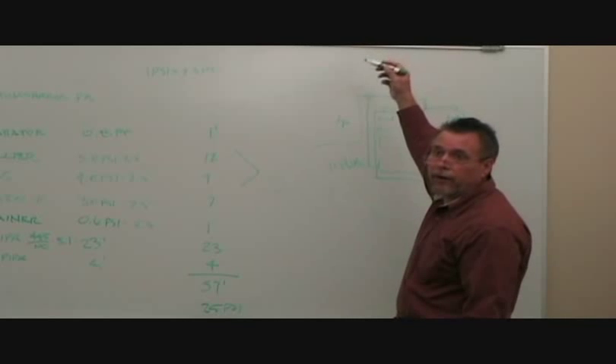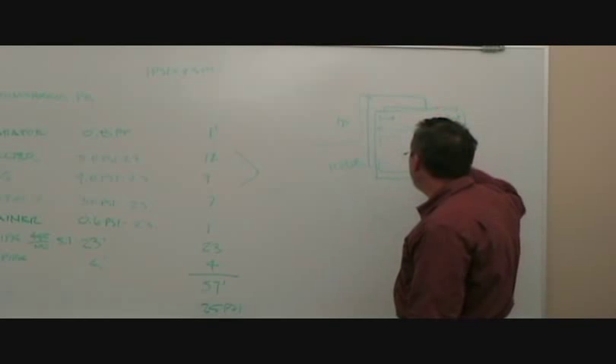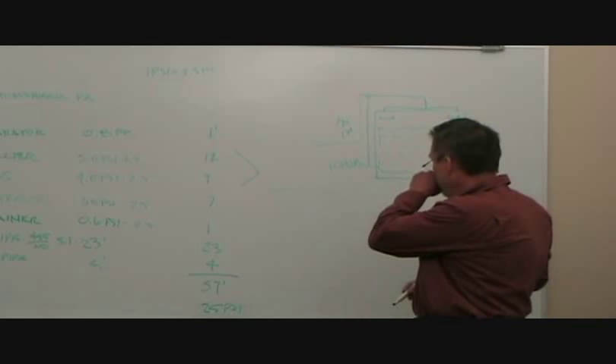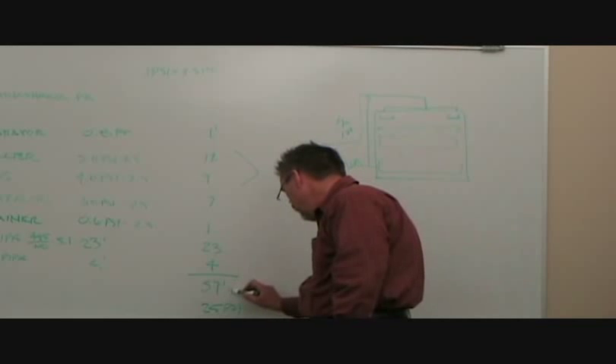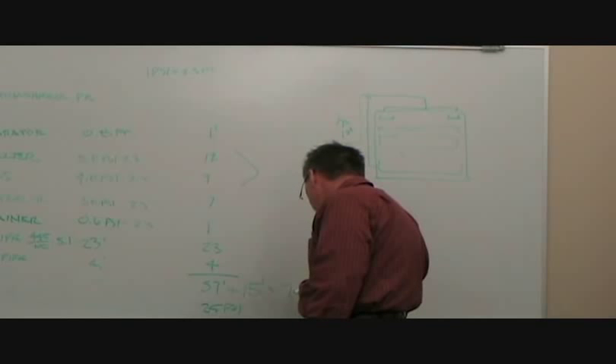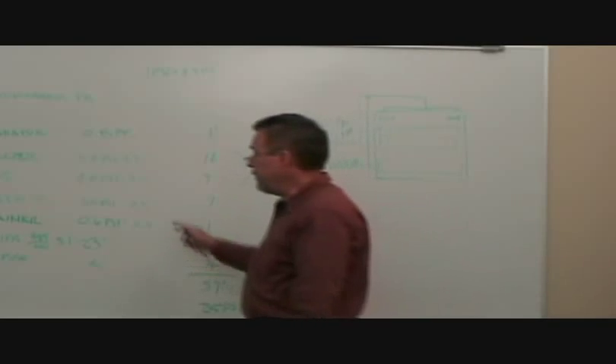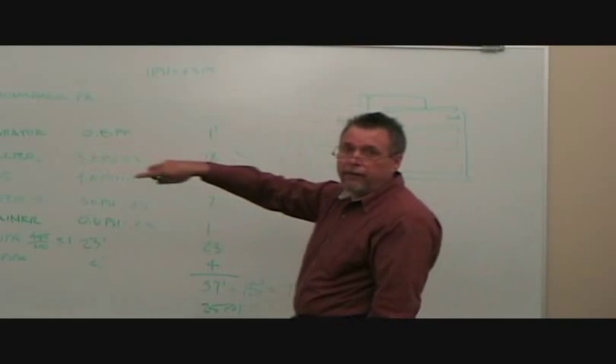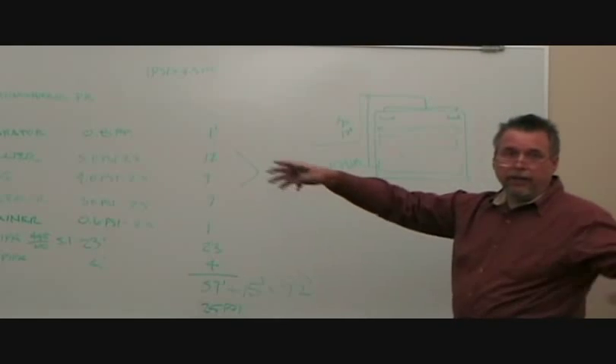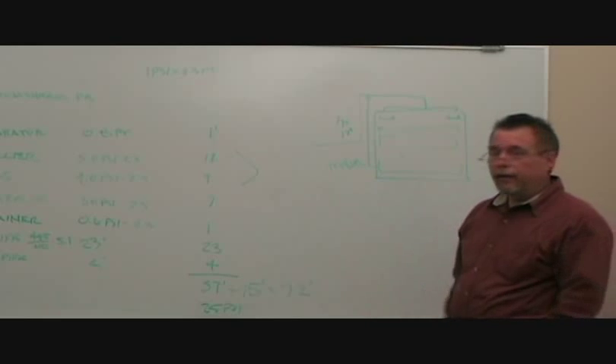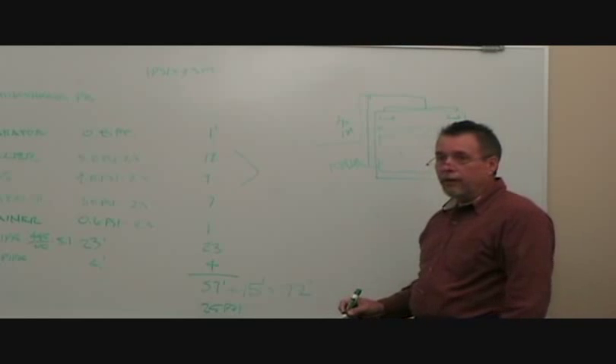Then I've got to lift that water up because it's open inside here, so that cooling tower is 15 feet tall. I have to actually add 15 feet right here to come up with 72 feet. I'm not saying that the pressure drop's the same on the chiller side as on the tower side, because there's going to be a lot less pipe.